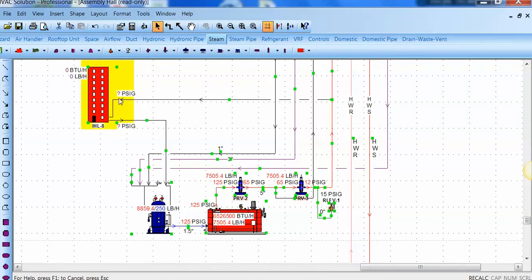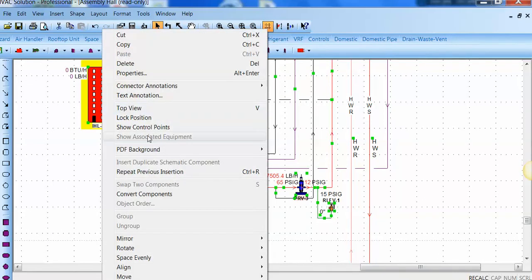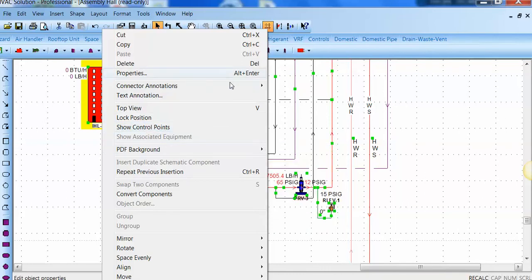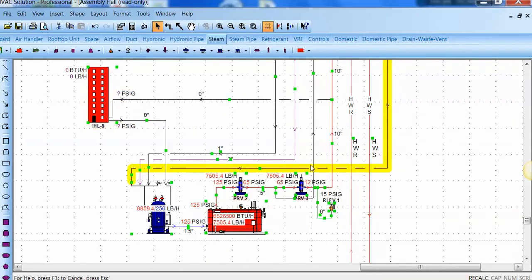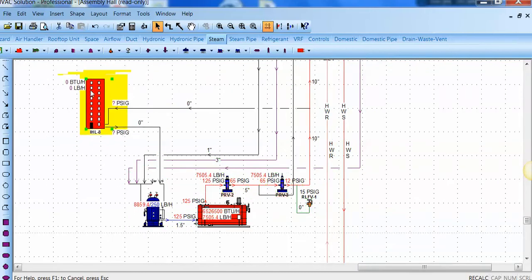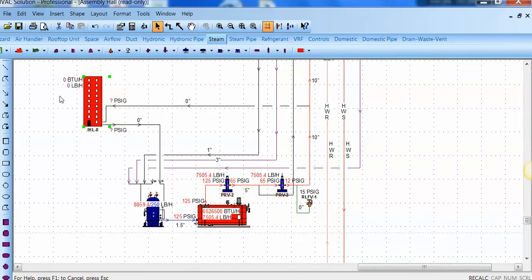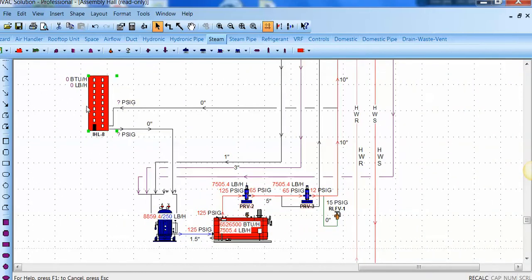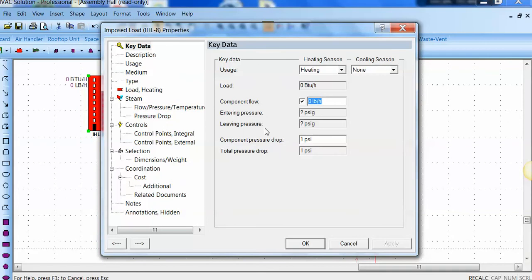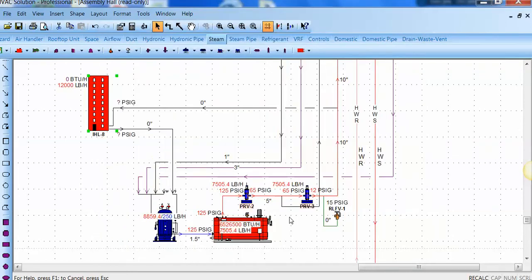Let's bring those pipe sizes back up. And this really goes to the core of the power of the software, where changes that might take days and weeks to calculate can be done in a few minutes. Again, we have a 10-inch main. If I add a load now to this future building, and our existing load is 7,000 pounds of steam, let's make this 12,000 pounds of steam. I push OK and hit Calculate.